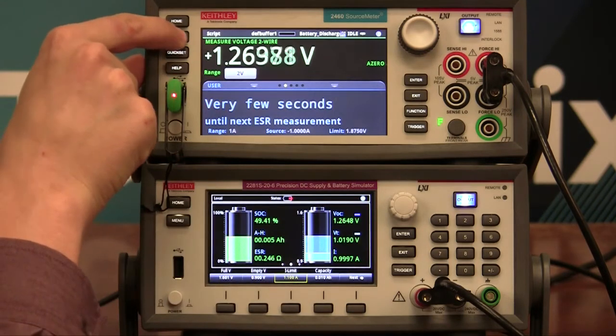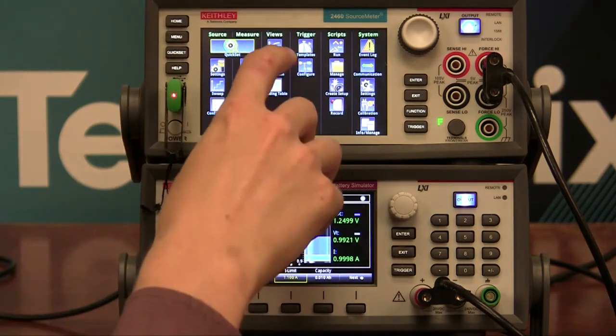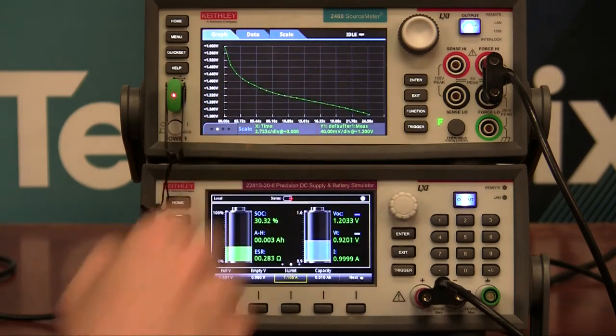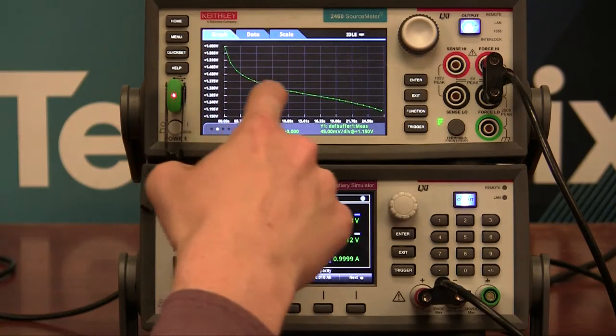So if we want to see this battery discharge profile as it's going, go to menu in the 2450, 60, or 61. Go to the graph. And now you can see it discharging.